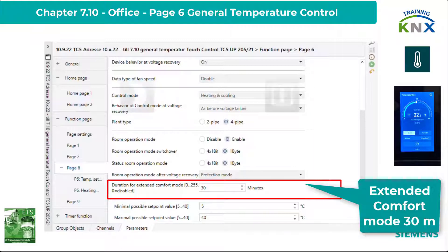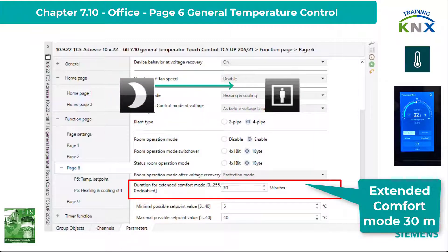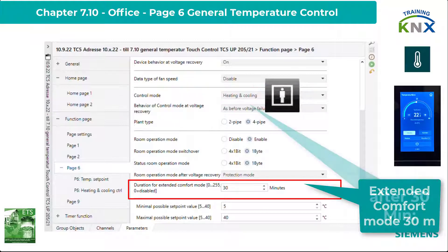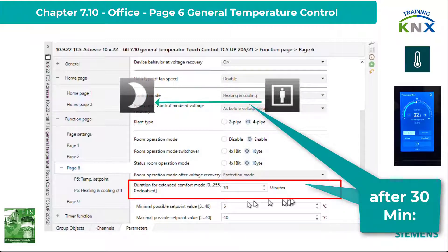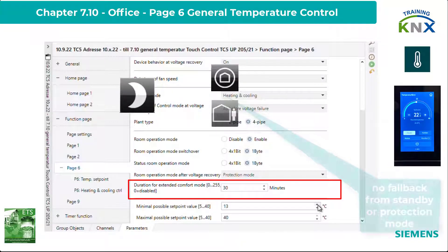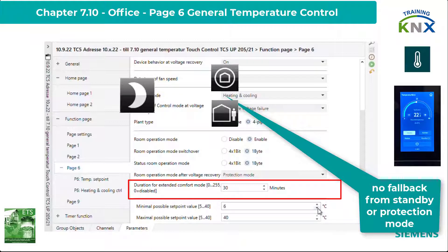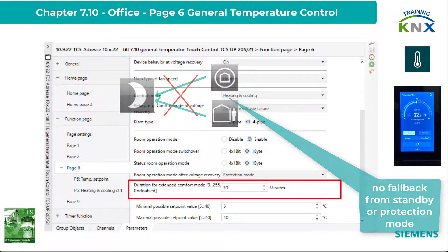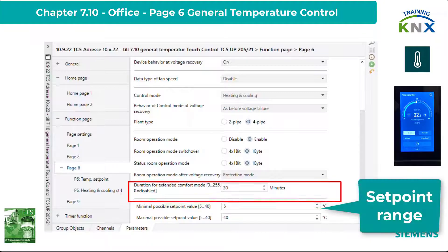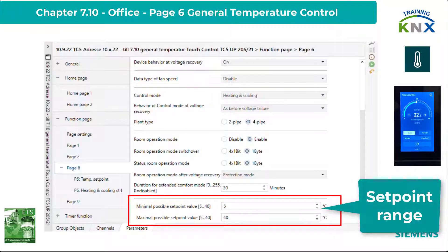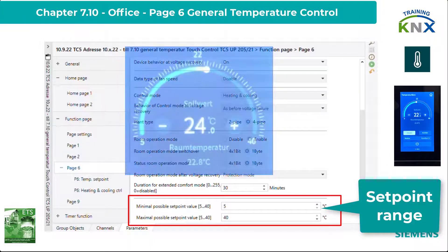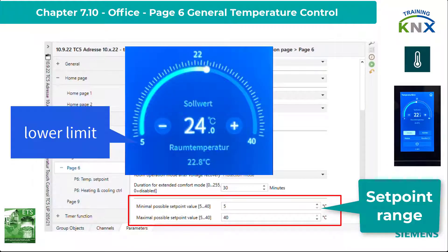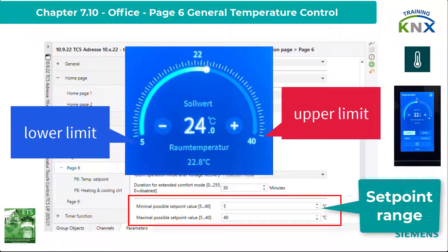The extended comfort mode is activated with 30 minutes, meaning the controller remains in comfort mode only for the set time but then switches back to eco mode if it was previously switched to comfort mode coming directly from that mode. If it has been switched to comfort mode via protection or standby mode, this timer does not apply. Finally, we can still adjust the setpoint range, but be careful: the restrictions made here apply to all possible operating modes.